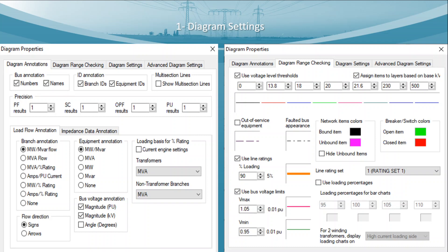In the second section of Diagram Properties, Diagram Range Checking, you can define voltage level thresholds with different colors, and also define your line loading limit — for example, if the loading of a line exceeds 90 percent, the color of the line will change. You can also define the thresholds for substation voltages; in normal cases, mostly a five percent criteria is used, and in contingency analysis, a ten percent criteria below and above the normal values is applied.